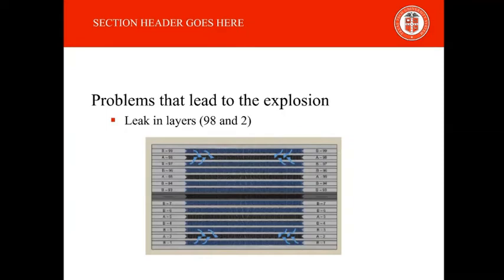In September 2015, HETSCO, a third-party service provider, repaired interpass leaks in the outermost layers of the exchanger. There was a leak in layer 98 and layer 2, as you can see in the figure. So they decided to weld the inlet and outlet of layers 99, 98, 2, and 1 shut, and leave layers 97 and 3 open to the process. The leaks could have possibly been coming from either of the adjacent layers, but it was treated as if the problem was not in layers 97 or 3, which can be seen in the figure. This crucial engineering decision is the first of many service-related failures that caused the accident on June 27th to occur.